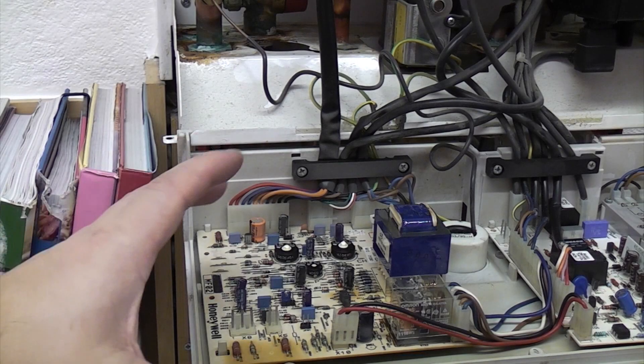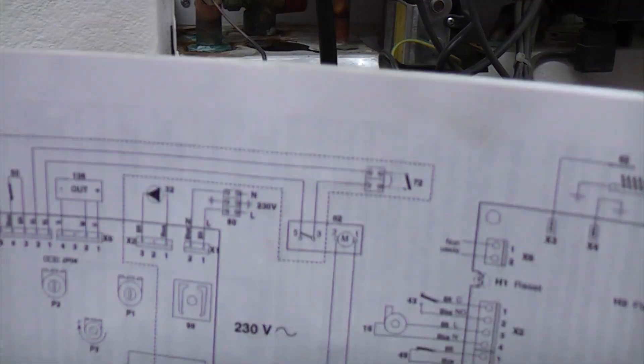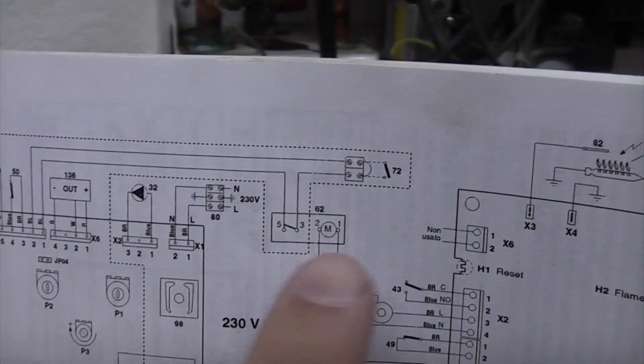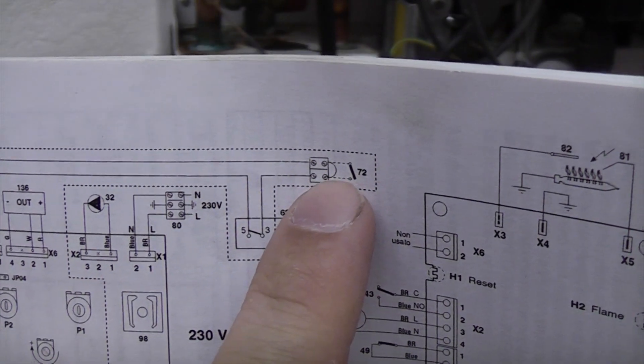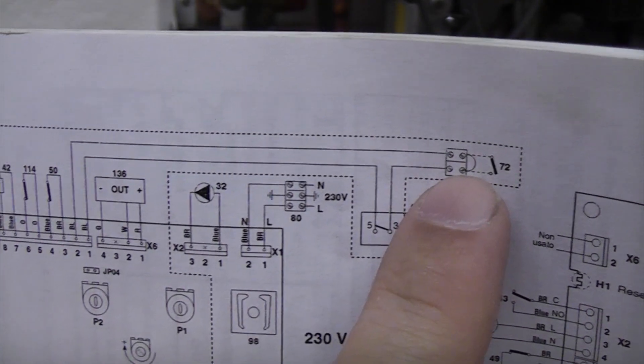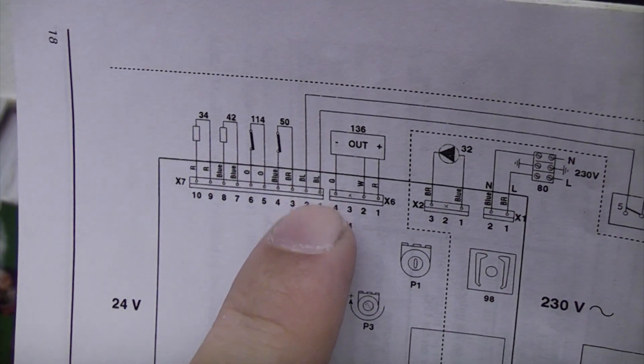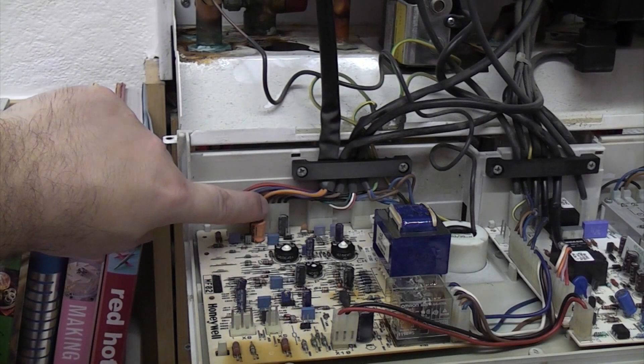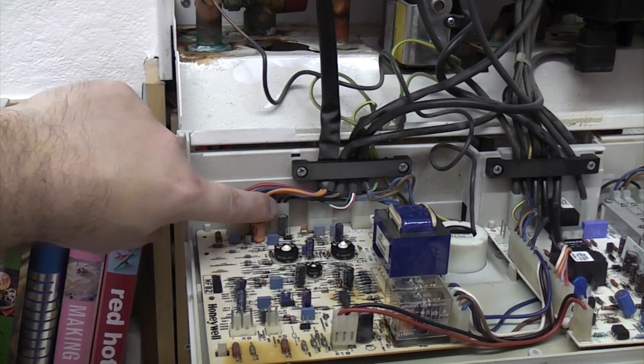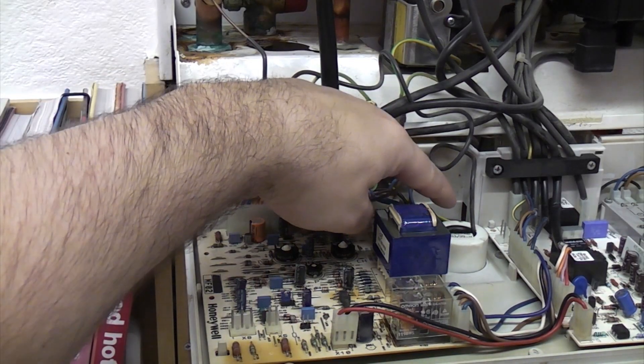So I have now got the PCBs in view, and they have also got the manual here, and we need to connect the room thermostat there to that terminal. But I haven't actually found it yet, so what I have did is I have traced the wires back there to those two black wires in terminals 1 and 2, which are those two terminals there—terminals 1 and 2, the two black wires, and they actually go across there and down there.